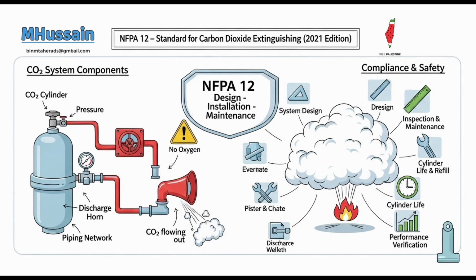Next is approval of installations. Once the system is complete, it must be thoroughly inspected, tested, and documented by qualified personnel for AHJ approval, using only listed or approved equipment. Inspected and tested by qualified people. This includes a thorough visual inspection and rigorous operational tests. Critically, full discharge tests are highly recommended and rarely waived. Actually firing the system off. Yes, because factors like extra cost or interruptions to production are explicitly not considered valid reasons for waivers. No excuses not to test it fully.